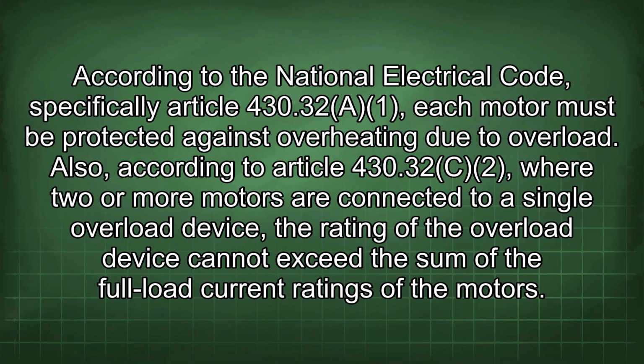According to the National Electrical Code, specifically Article 430.32(A)(1), each motor must be protected against overheating due to overload. Also, according to Article 430.32(C)(2), where two or more motors are connected to a single overload device, the rating of the overload device cannot exceed the sum of the full load current ratings of the motors.